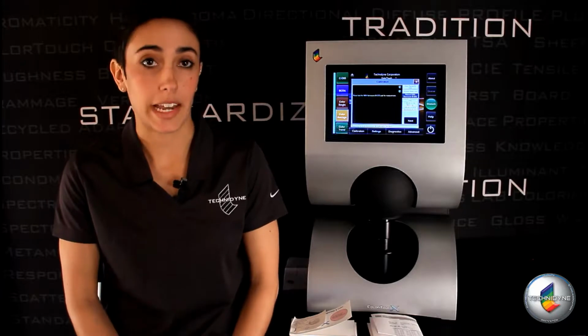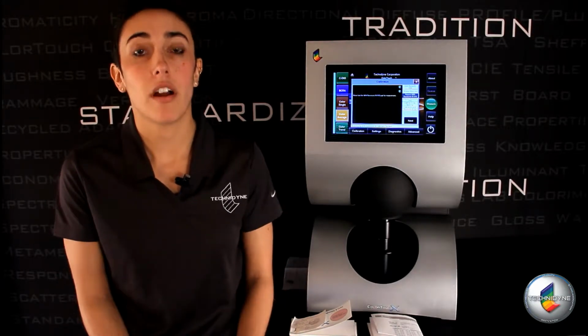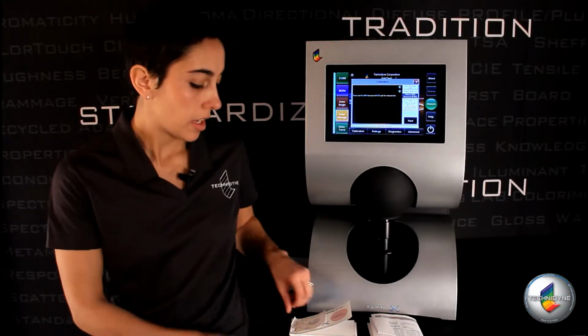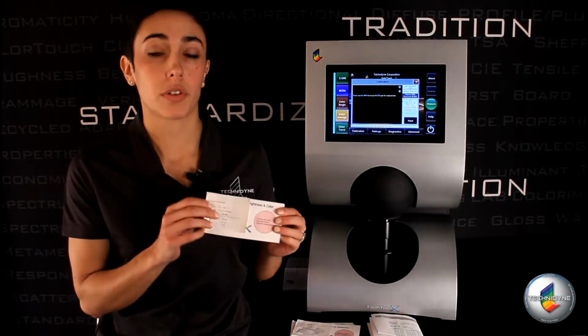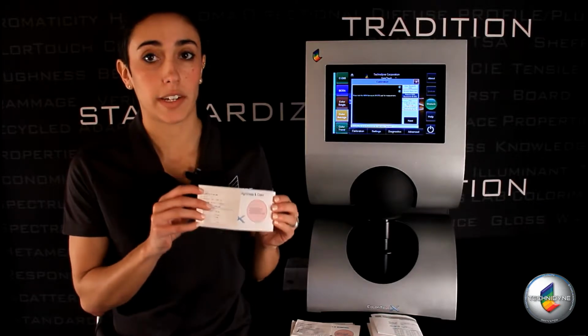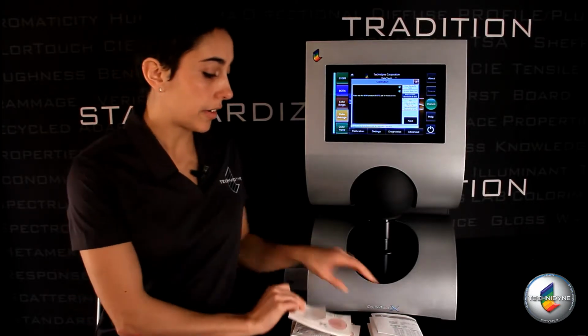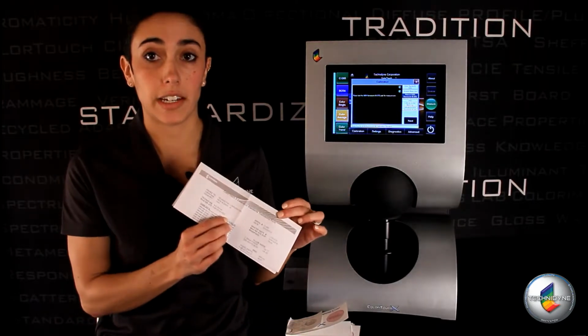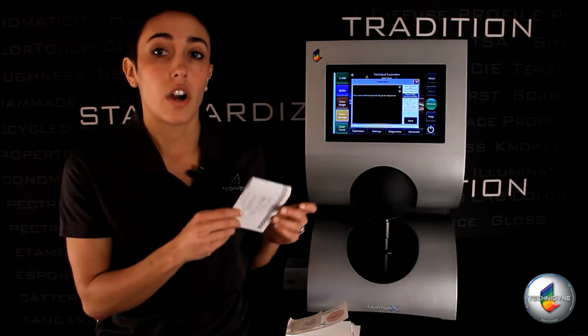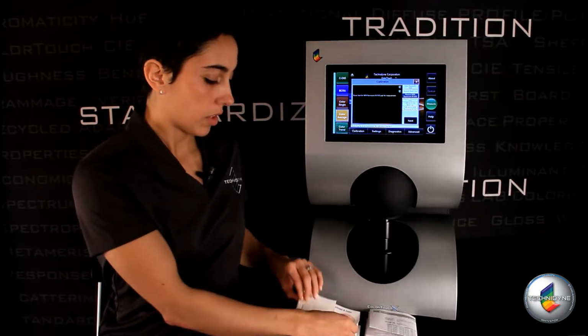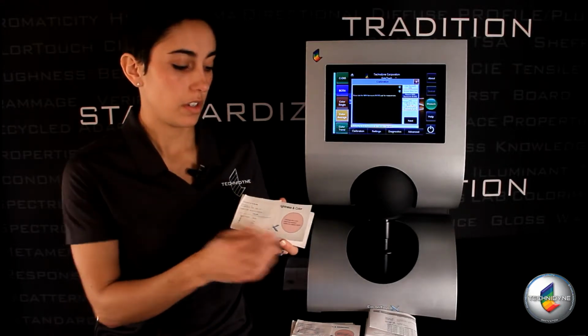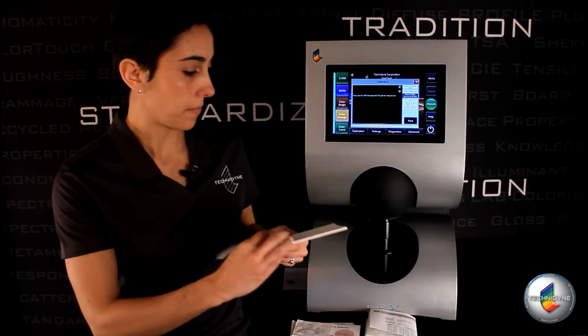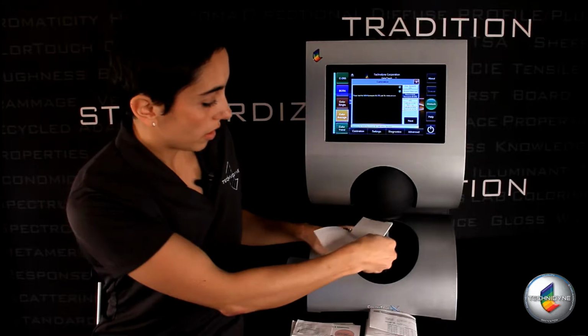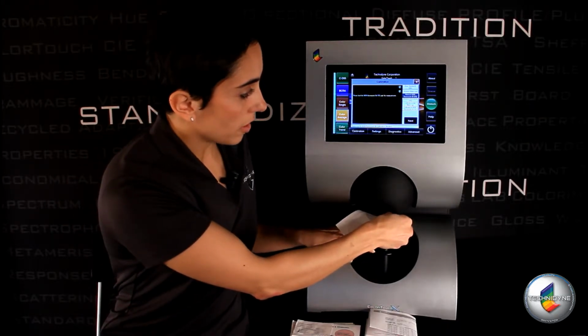Once the black cup setting is done, the software is going to lead you to the next step, which is to measure the non-fluorescent 90 standard. But before we do that, we want to make sure that the serial number on the non-fluorescent 90 standard matches the serial number on your data sheet as well as the serial number on your USB. Once you've made sure of those, you'll fold back this top page. You'll load your standard and you'll hit next.